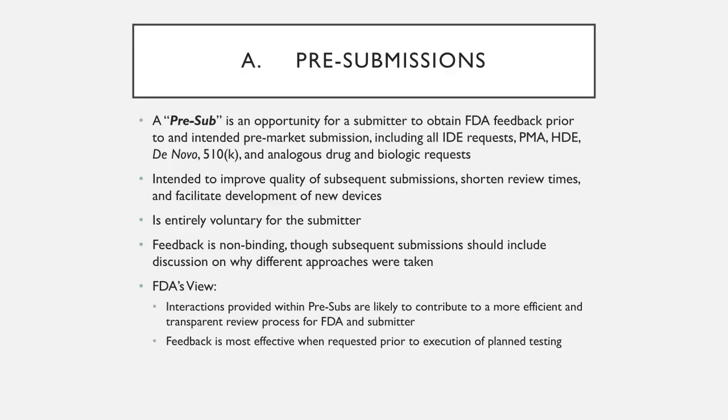Now, the feedback that the FDA gives is not binding in any kind of legal sense, but the subsequent submissions should include discussions on why different approaches were taken, and it's always up to the purview of the medical device company, who knows the most about their particular medical device, to justify why any choices were made. From the point of view of the FDA, any interactions provided within the pre-sub process are going to contribute to a more efficient and transparent review for the FDA and the submitter. And in line with the purpose of the pre-sub process, any feedback that's expected from the FDA is most effective when requested prior to executing a planned line of testing.